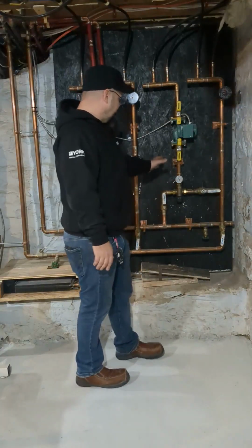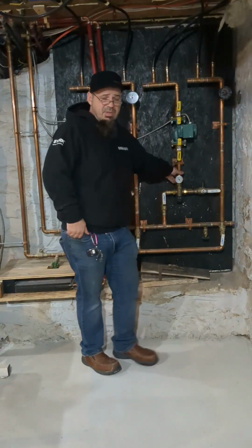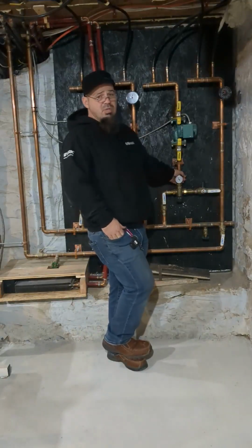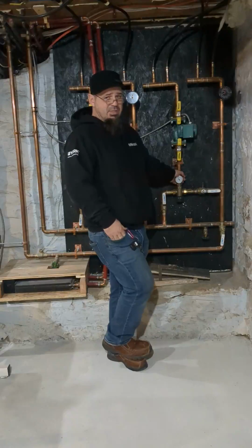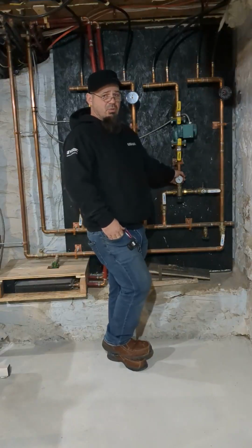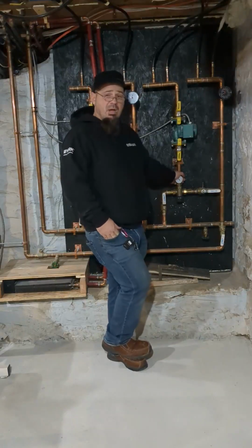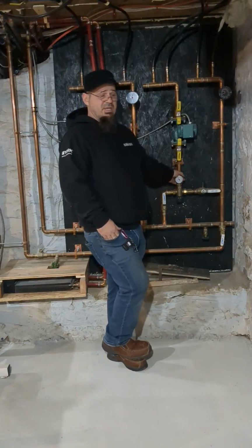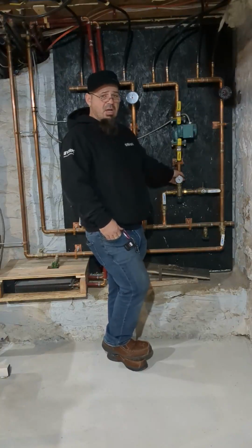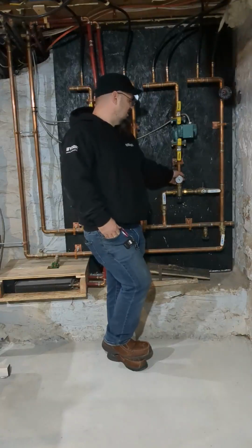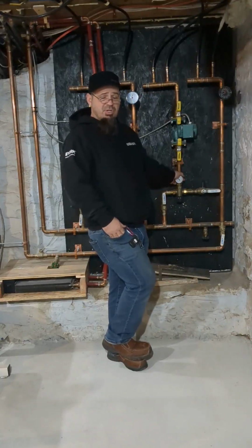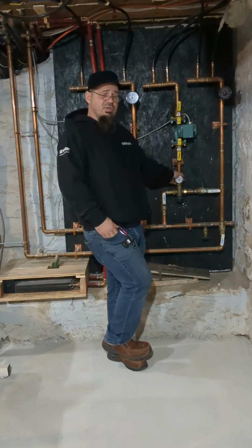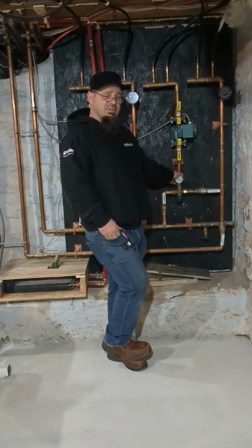Okay, so one of the number one mistakes that people make is overheating their Radiant floor, and let me tell you, you can do a lot of damage by overheating your Radiant floor. Sending out supply water temperature that is too hot can damage wood floors, it can buckle things, it can cause all kinds of problems. So understanding what type of substrate you're working in and how it's applied is essential to making sure that you keep the construction materials in the space safe.